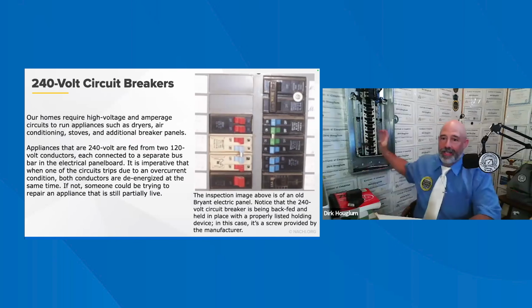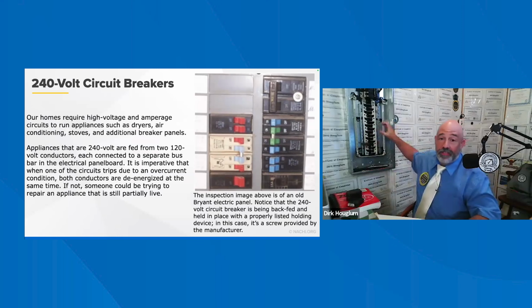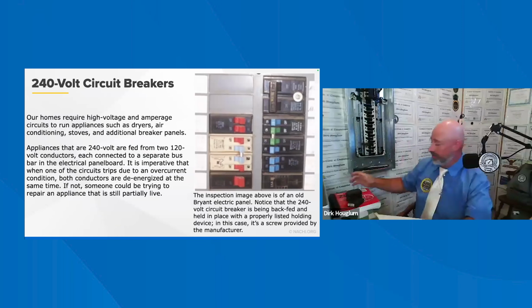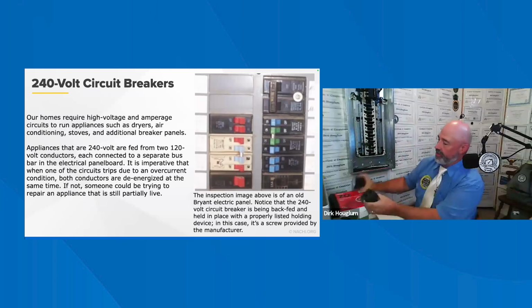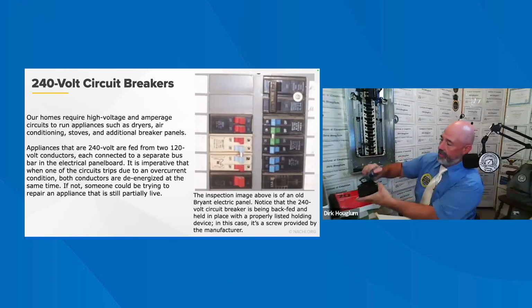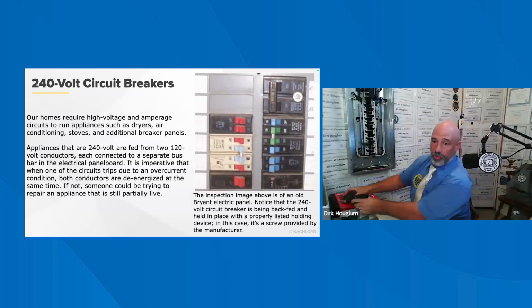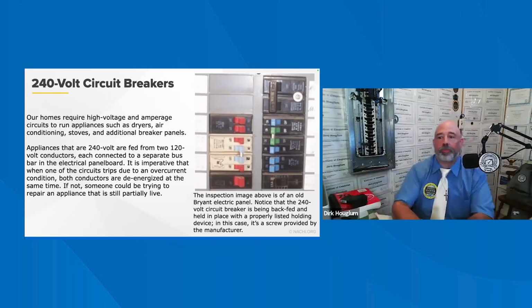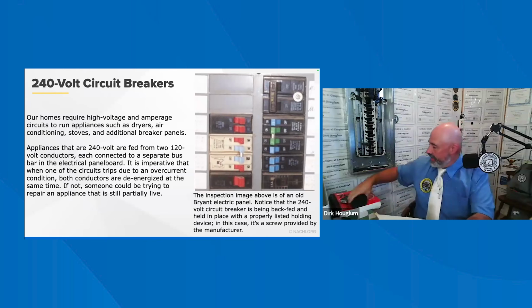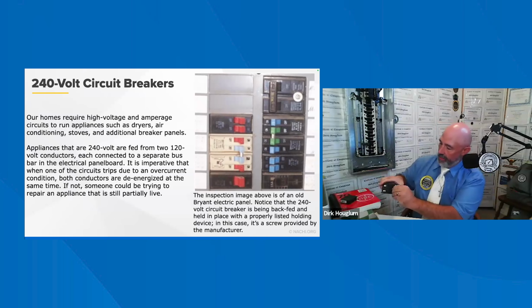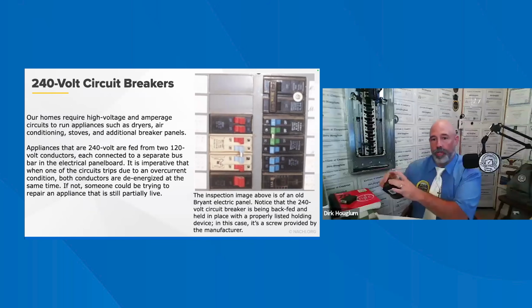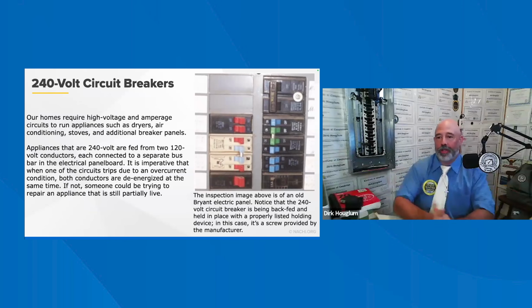We've just seen how I did that, and it clips right into place. And these are called tandem breakers. As you can see, there are 2, which means tandem. I always think of the tandem trailers. Okay, for that reason, all breakers supplying 240 volts are required to have their handles tied. So this has a handle tie on it. I can actually remove this handle tie, but then it becomes 120 and 120. So that's why you get the 240.